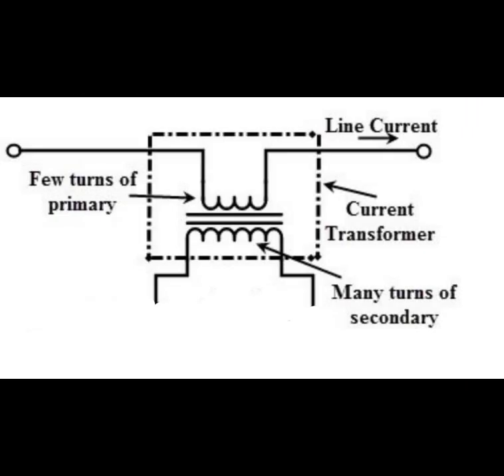When the secondary circuit of a current transformer is open-circuited, no current flows in the secondary winding. However, the primary winding is still carrying its rated load current. As a result of this, a very high voltage will develop across the open terminals of the secondary winding due to the inductance of the winding.